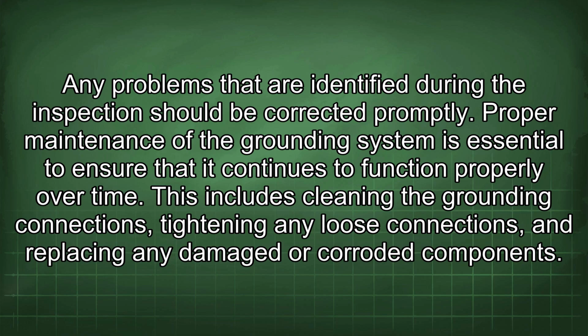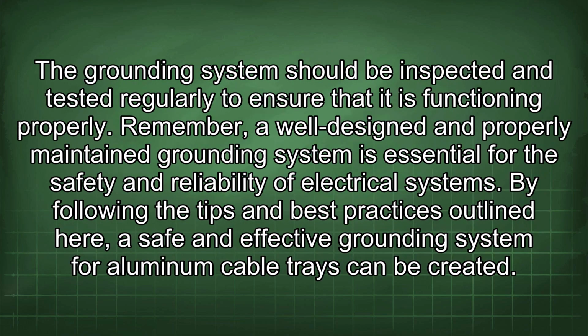Proper maintenance of the grounding system is essential to ensure that it continues to function properly over time. This includes cleaning the grounding connections, tightening any loose connections, and replacing any damaged or corroded components. The grounding system should be inspected and tested regularly to ensure that it is functioning properly.